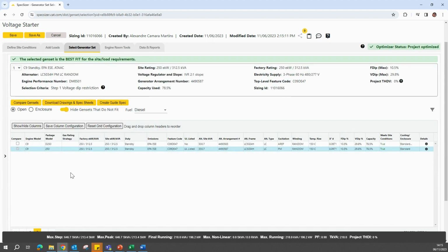By using the Y delta starter, we can see now that the recommended generator set is a C9. The package was reduced from a C27 engine to a C9 engine. If we look at the capacity now, it's using 78.5%. That means we now have a generator set with a running load that matches its capabilities.